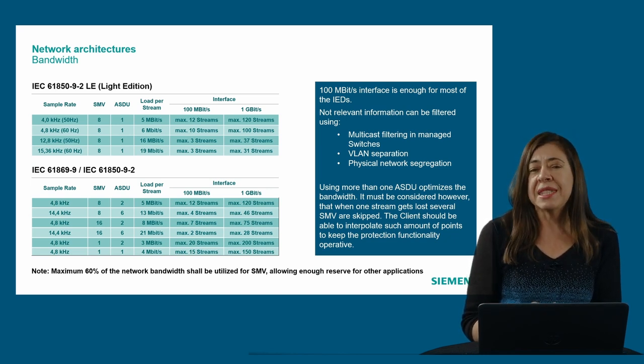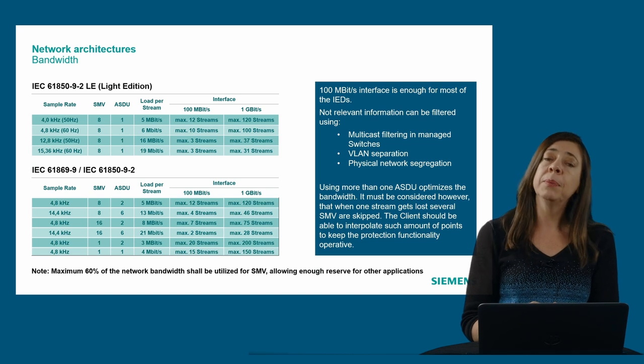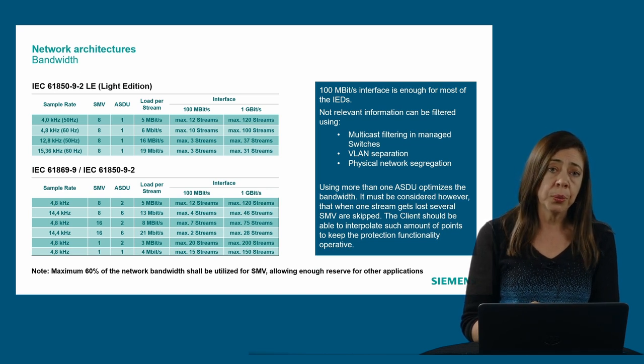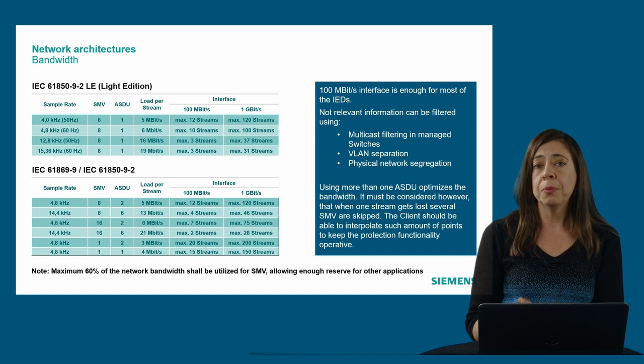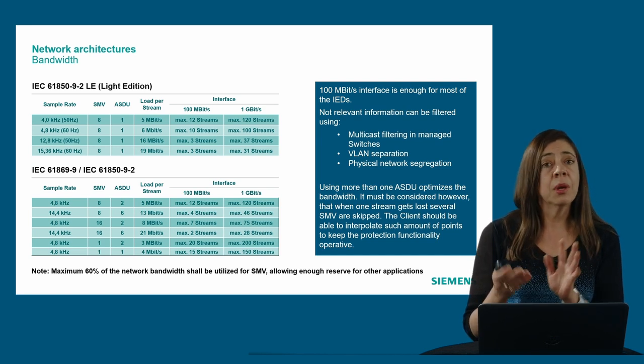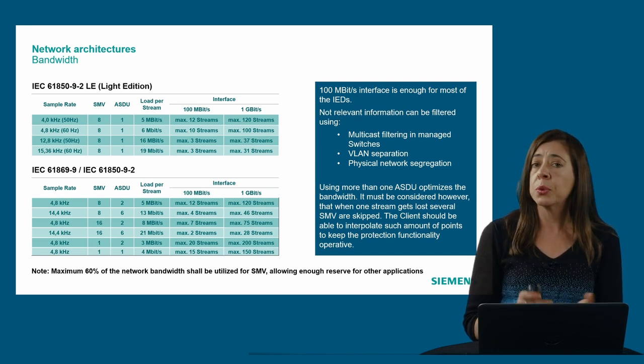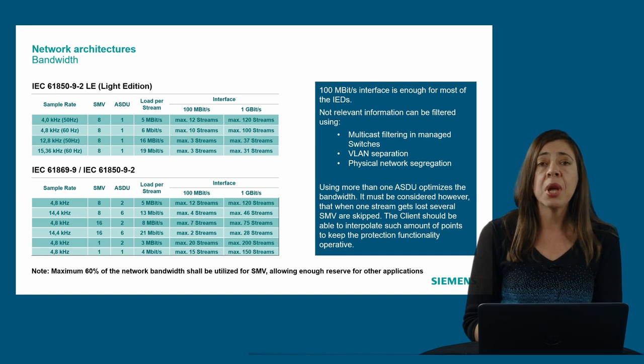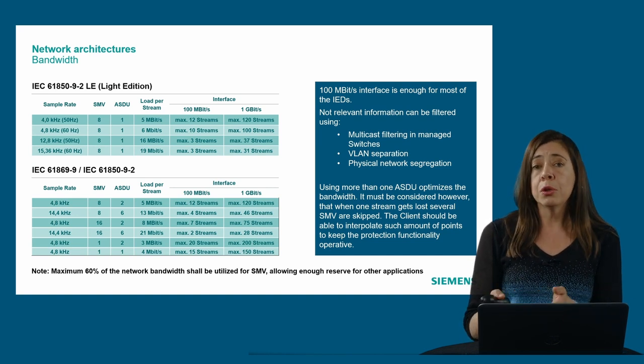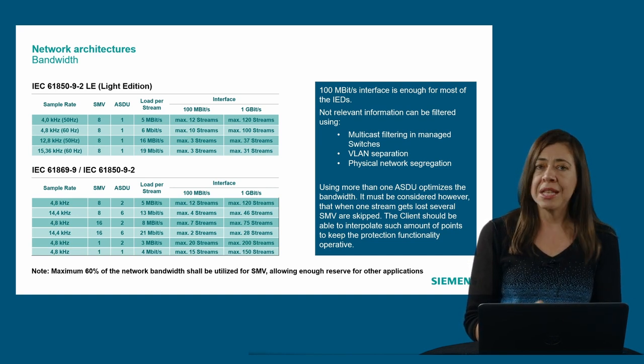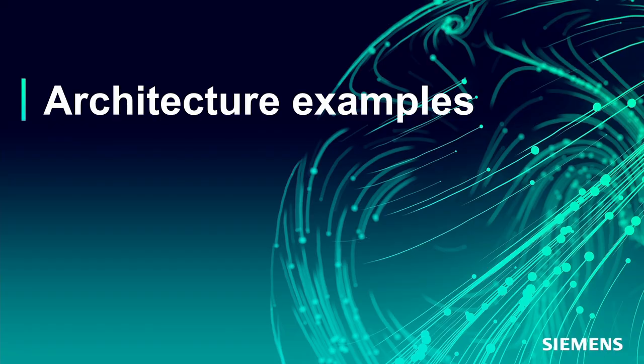As a design value, keep the use of the network below 60% for sampled measured values. In such a way, you can be sure that all other messages, such as GOOSE messages or synchronization messages, can also be transmitted without any risk of overflow. So now let's see some architecture examples.